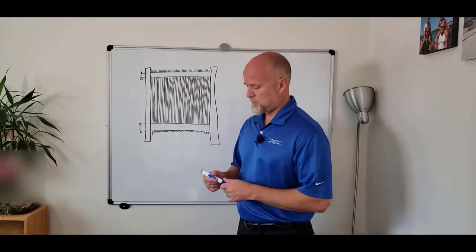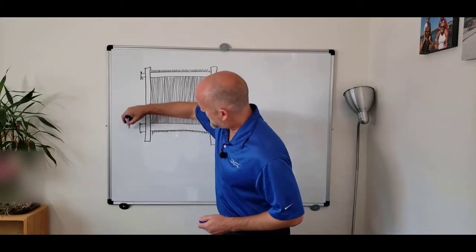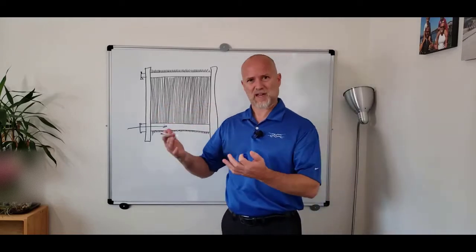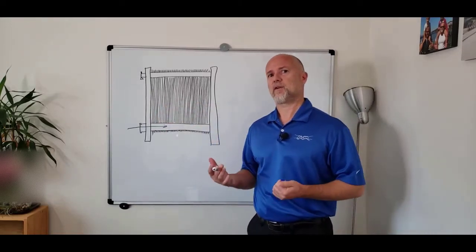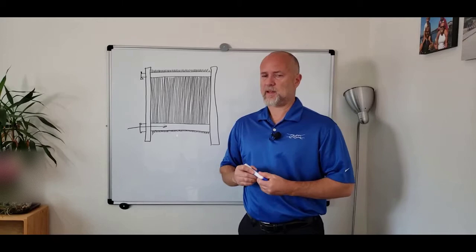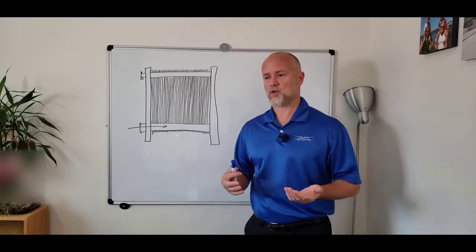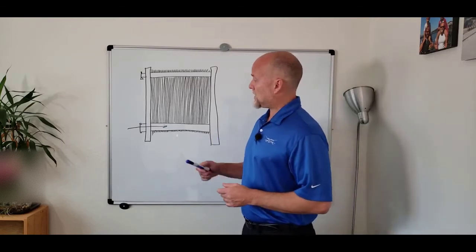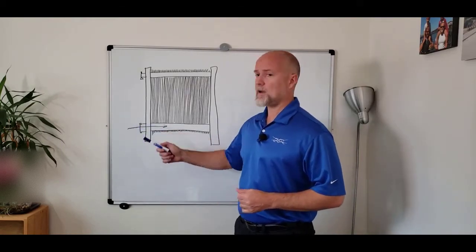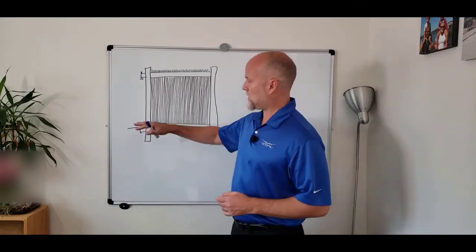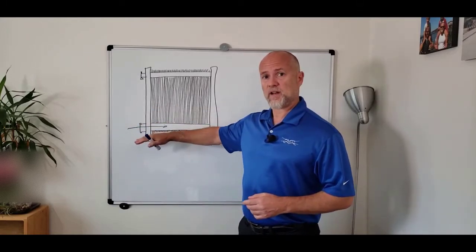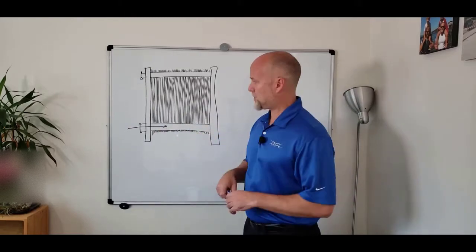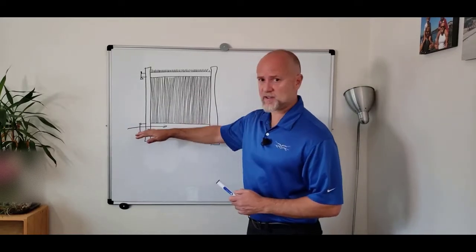Well, first of all, if you imagine this is the inlet, let's say the cold inlet, which normally is the more challenging because it comes from the cooling tower so you might have debris, you can have fouling issues. So the cold inlet normally is the most challenging one. And that's the reason why we suggest to always put it at the bottom of the heat exchanger and not at the top so you can take advantage of the positive pressure coming from the pump.